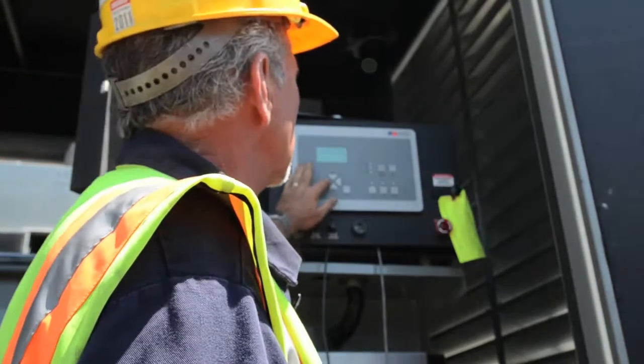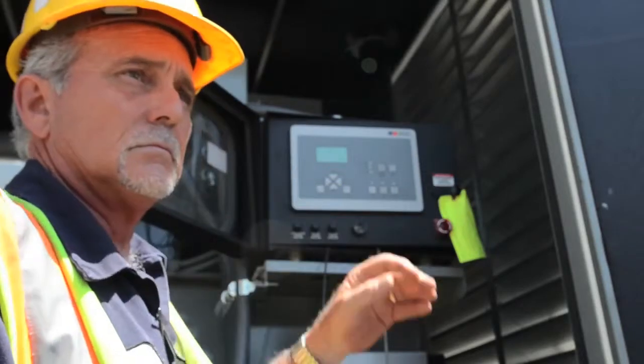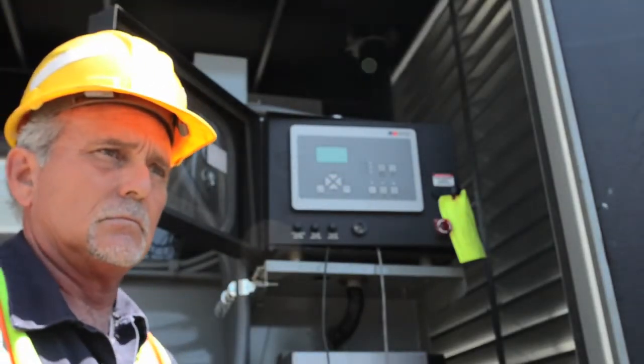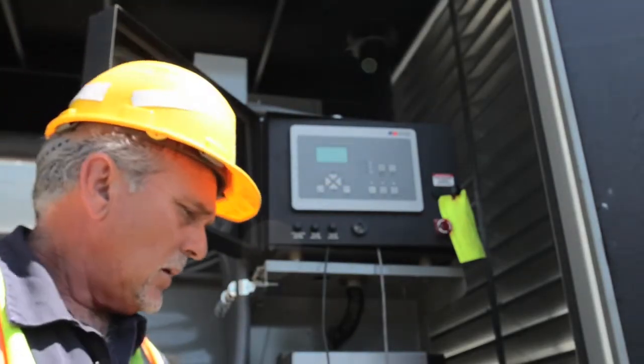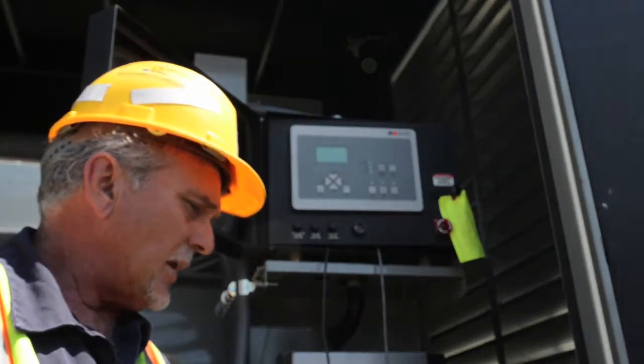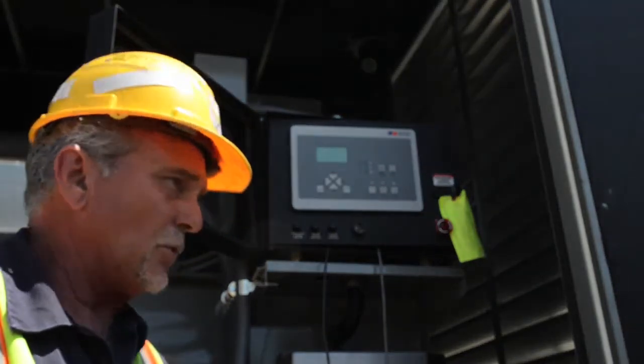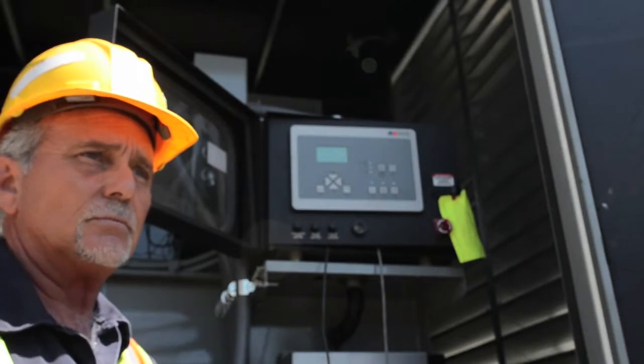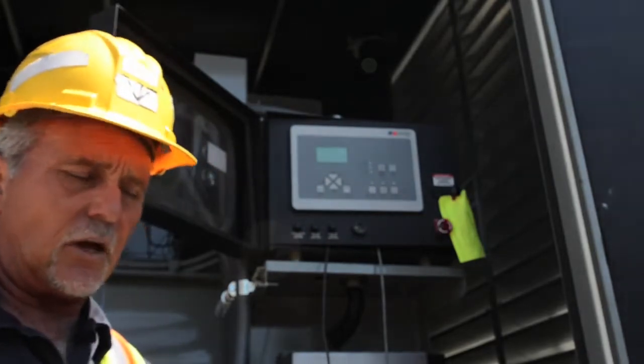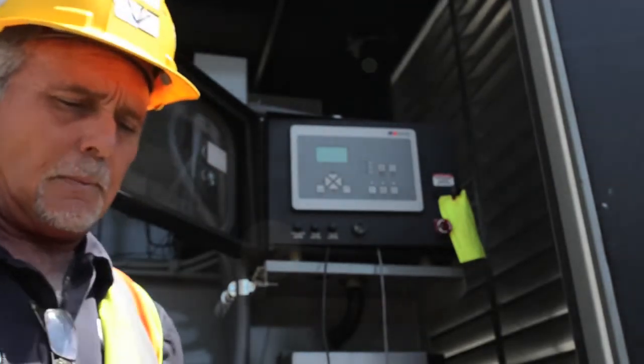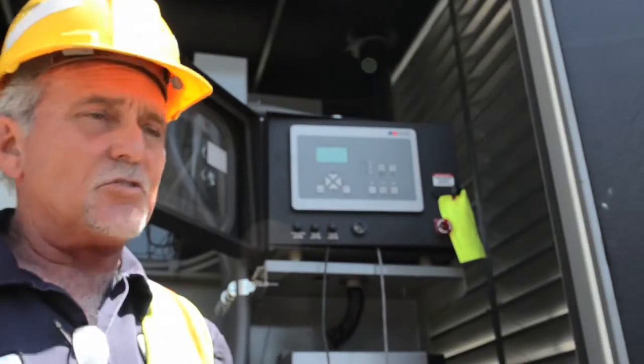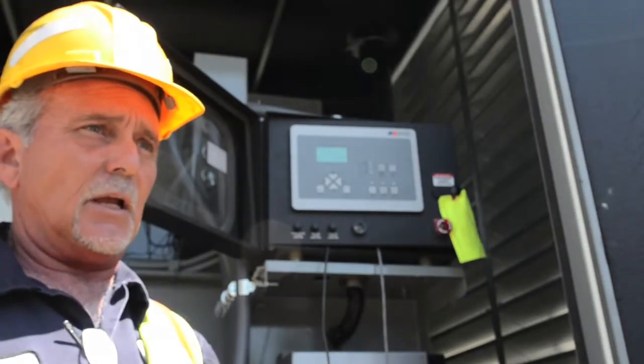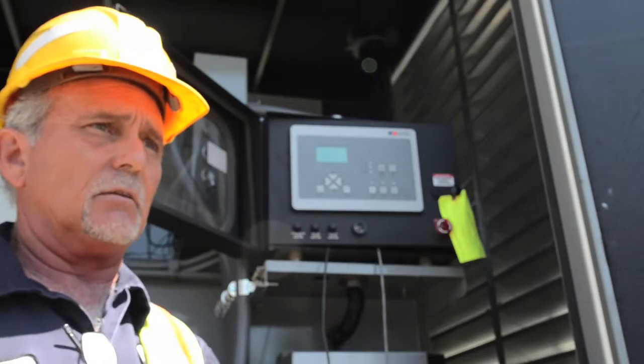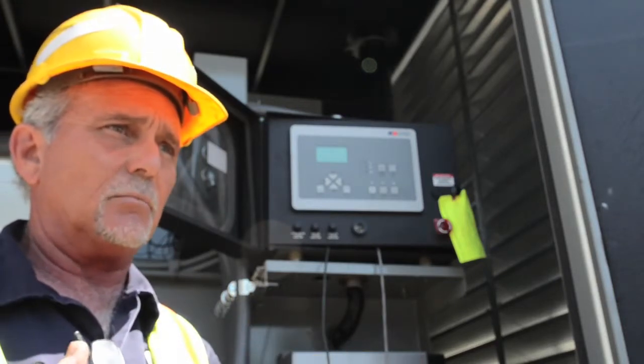On the genset, loaded and unloaded - does running it unloaded damage anything compared to loading it? Well, every generator is built with what they call taper cut piston rings, designed so that when the engines don't have any boost pressure and just start up - generators don't idle, they start up and go straight up to 1800 RPM.